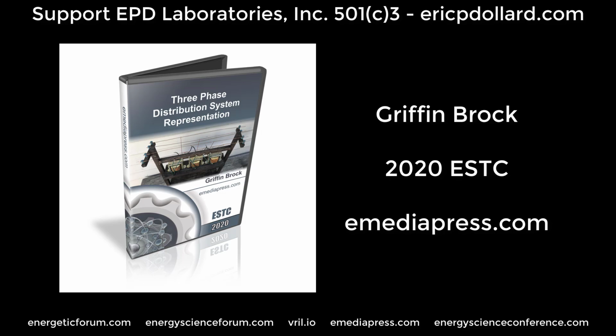So the thing to do is find the capacitor that will resonate with the motor when it's spinning at 60 cycles. Then it becomes self-exciting, and you won't be able to control the voltage, but you'll have it. That's probably your way out. If you want to use an induction motor as a generator, you find the right capacitor to connect to self-excite it, and then it'll work as an alternator.